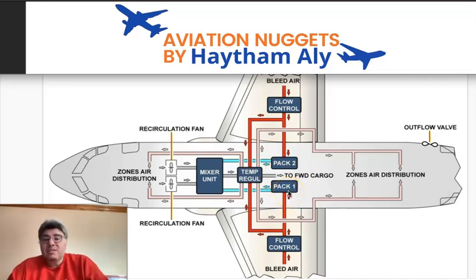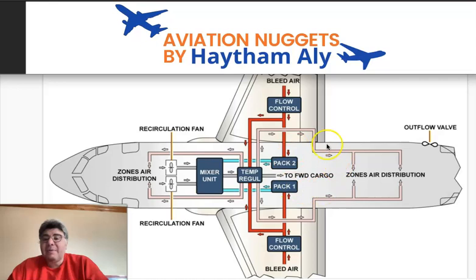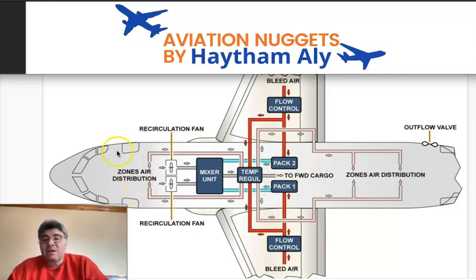How many zones inside the fuselage will the packs supply? We have three zones: the cockpit, the forward cabin, and the aft cabin. The pilots have three selectors to individually select the temperature in each zone. PACK 1 supplies the cockpit, and PACK 2 supplies both the forward cabin and the aft cabin.